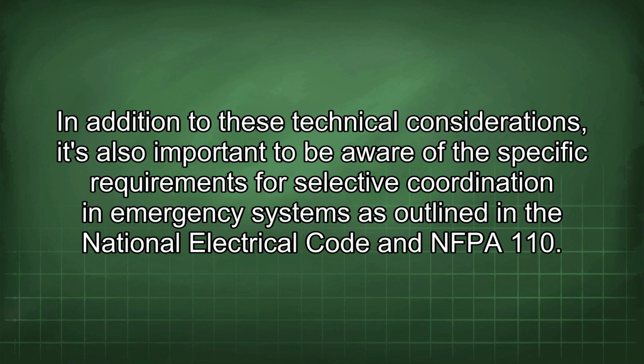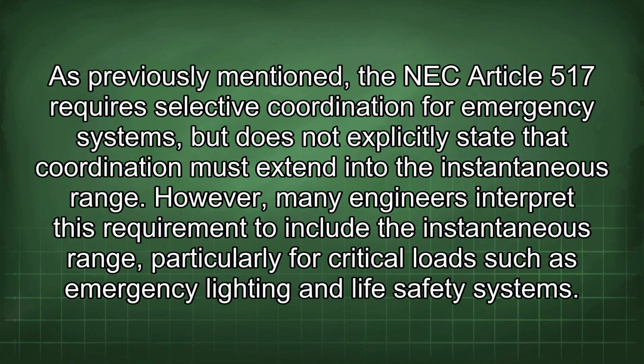In addition to these technical considerations, it's also important to be aware of the specific requirements for selective coordination in emergency systems as outlined in the National Electrical Code and NFPA 110. As previously mentioned, the NEC Article 517 requires selective coordination for emergency systems but does not explicitly state that coordination must extend into the instantaneous range.